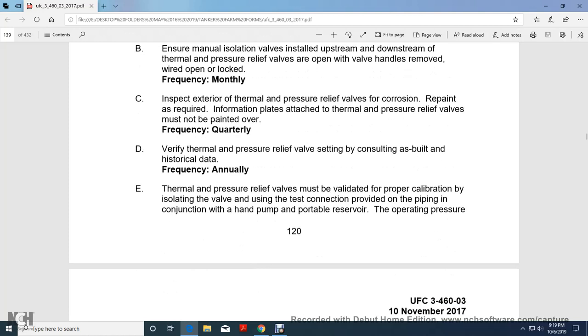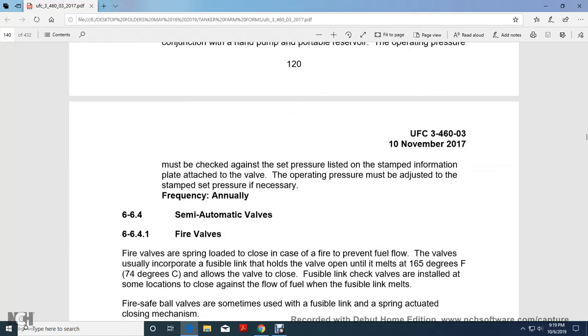Thermal pressure relief valves must be validated using the proper calibration isolation valve used for the testing connection provided with the piping, in conjunction with a hand pump with a portable reservoir. The operating pressure must be checked against the set pressure listed on the set information plate attached to the valve. The operating pressure must be adjusted to the same setting of the pressure as necessary, annually.